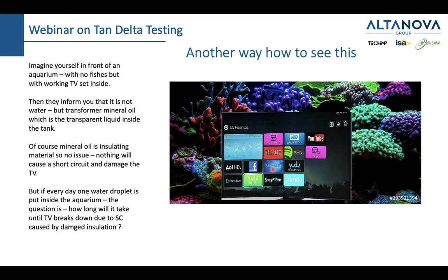But now imagine that you have this situation back home, and every day you put one drop of water inside that tank, and then you stir it up. After 5 or 10 days, probably nothing would happen. Maybe nothing would happen after 50 days. But if for 100 consecutive days you would be putting one drop of water inside and stirring, at one point in time there would be enough water inside that mineral oil to cause a short circuit. And that's what happens inside your power transformer. You have a transformer which breathes. We'll talk about that later. That transformer attracts water molecules inside, and the water molecules sooner or later can create a short circuit. So what we do here with Tan delta, we will measure and tell you when it is high time to get your TV out.